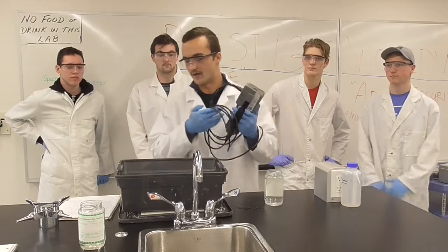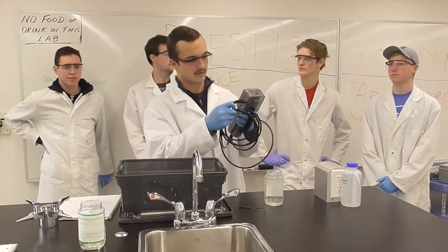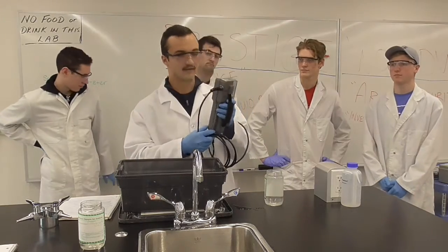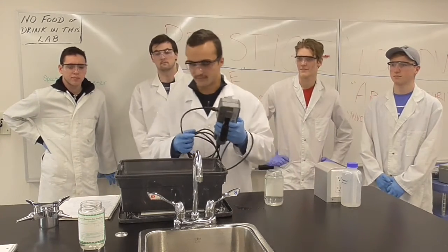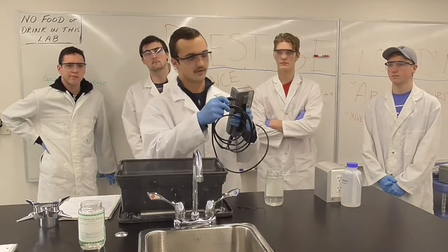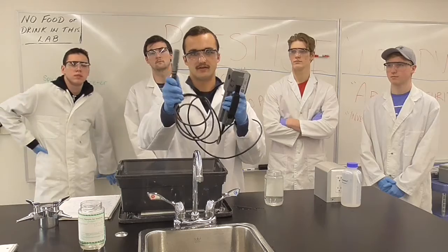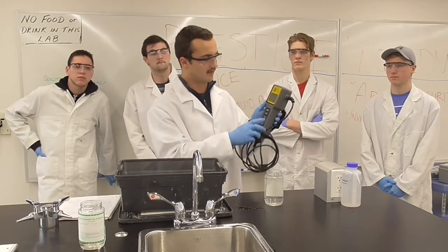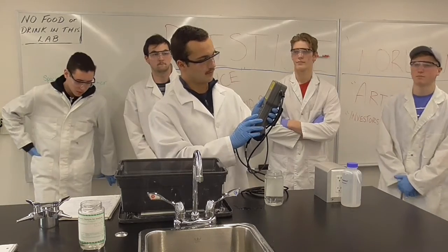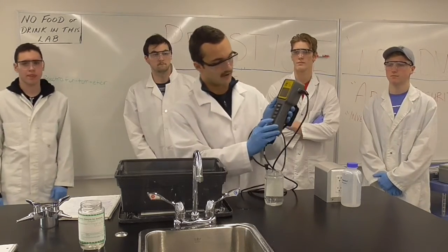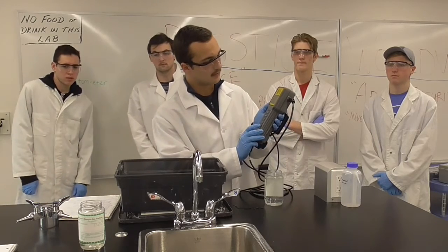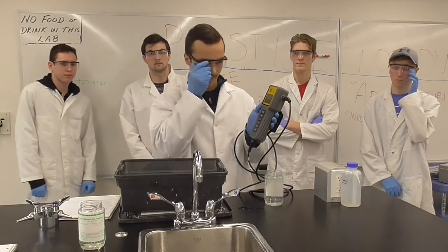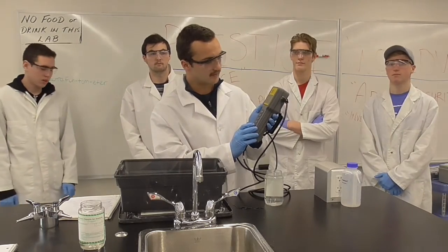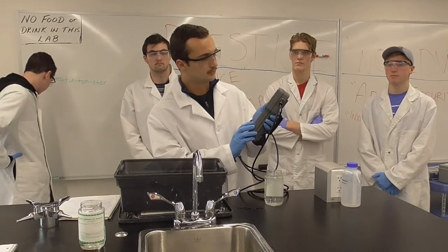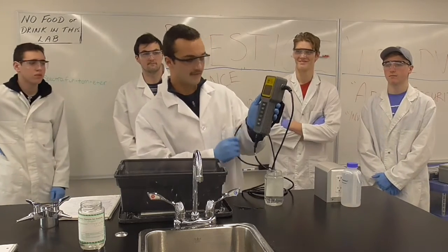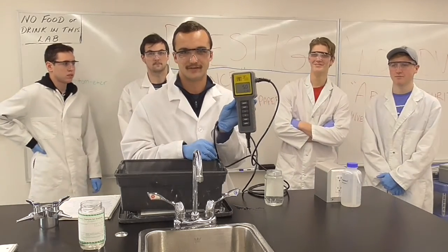So before we turn this thing on, we want to do a little physical check, make sure the cords are intact and it's in good physical condition. Once we've determined that, and the electrode is properly installed, as we can see here, we can turn the device on, and we'll wait till it turns on, and we'll go to the mode and select where it shows our degrees Celsius symbol, and we want to keep on hitting mode until that degrees Celsius symbol is flashing. It's not flashing. There it is. So now we see that it's flashing. I'm going to zoom in on that.